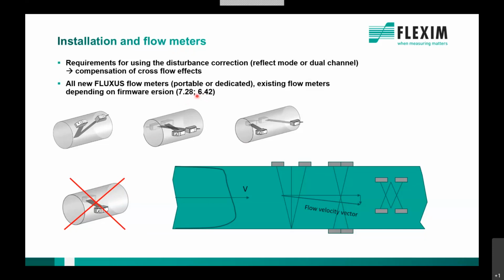What to do with existing flow meters? Well, make a firmware update. If you make a firmware update, you will profit from that disturbance correction because then it will be available. So it can be used for older meters as well. Does it make sense for already installed meters? Probably not, because you don't want to change it. Customers or users are used to what they're reading. You can, if you want to make it better, more precise. But from my point of view, the firmware update is necessary for portable meters, where it really makes sense to use that function.